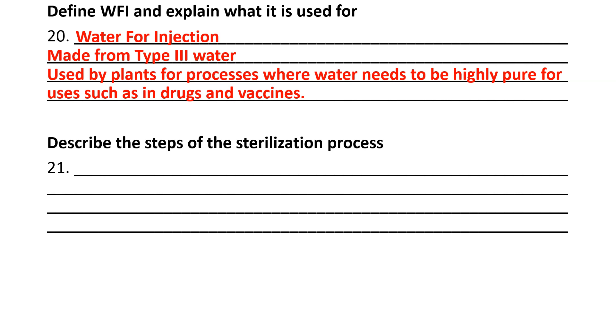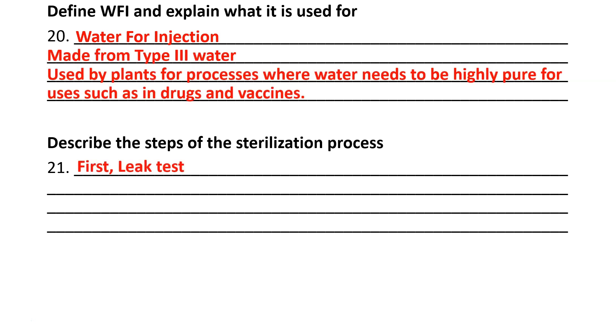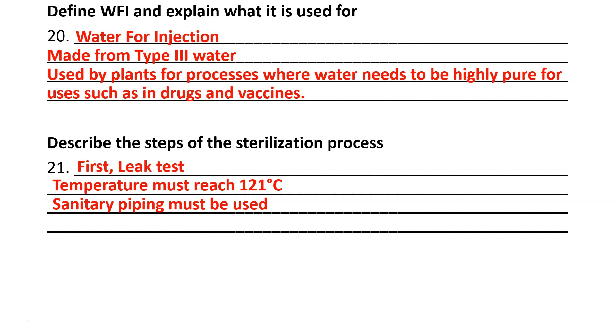Describe the steps of the sterilization process. First, you need to do a leak test — make sure there's no leaking occurring from the device. You must make sure the temperature reaches 121 degrees Celsius, which is very important for anything to be considered sterile, often at 15 psi gauge as well. Sanitary piping must be used, which means stainless steel and several other requirements: it cannot be flat, no 90-degree or sharp bends, and no places where liquid can collect and stagnate.